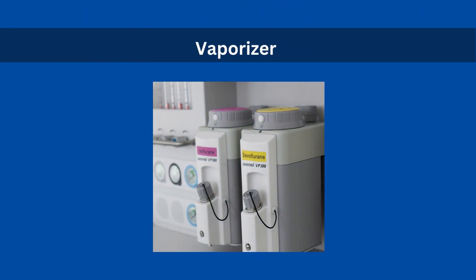Vaporizers are color coded to avoid wrong installation of volatile liquids — for example, isoflurane is purple, sevoflurane is yellow, while halothane is red. Vaporizers have a unidirectional valve to prevent backflow during positive pressure ventilation. They are also equipped with an interlock mechanism, which prevents more than one vaporizer from being used at the same time.